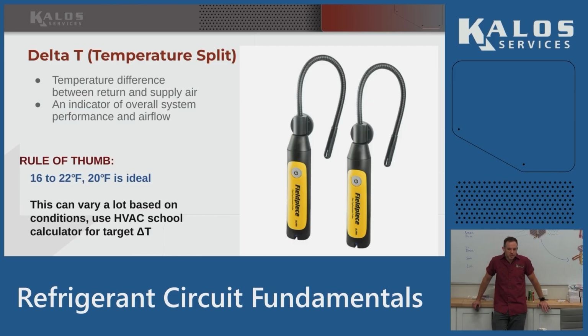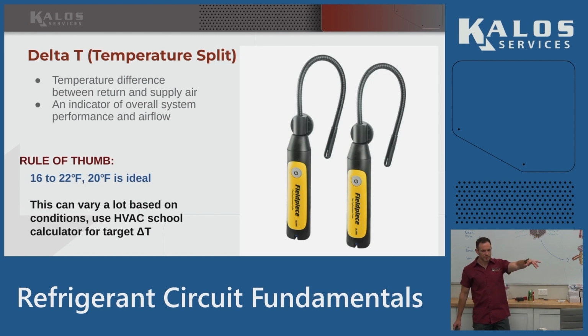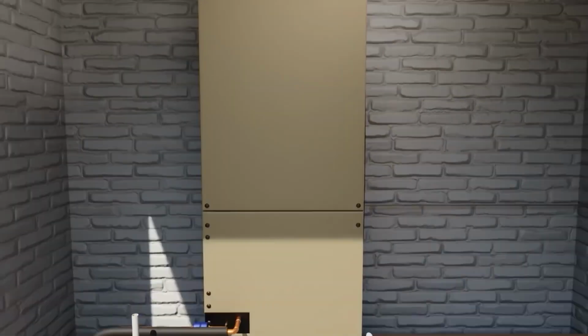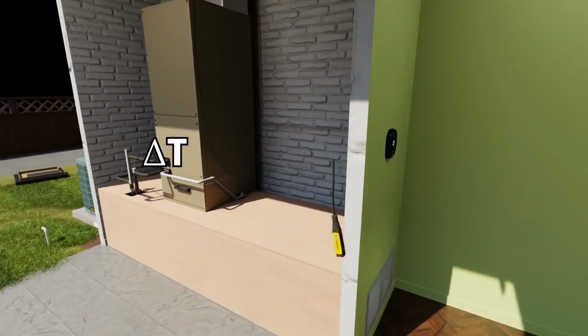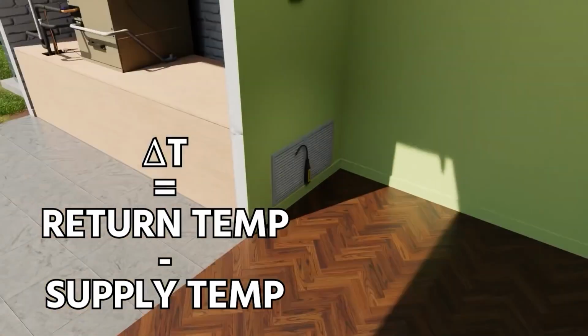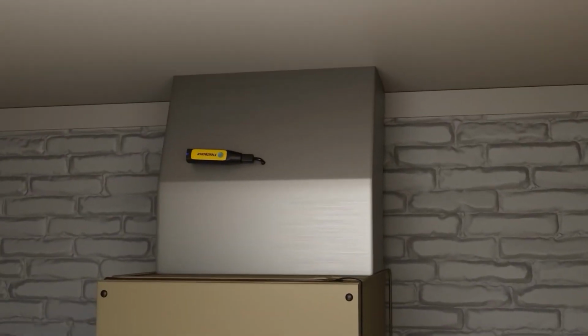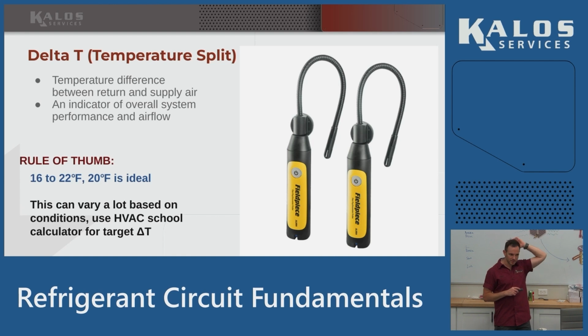If you're reading a poor temp split and you don't know if you actually have a problem or not, throw a quick calculation in there, because a lot of times relative humidity will play a factor in what you're seeing, and it doesn't have to be 20. Where we're putting our probes is one in the return, measuring return air, and one in the supply, measuring supply air, and we're looking at the actual sensible temperature difference between these two. How efficiently is our system cooling the air?